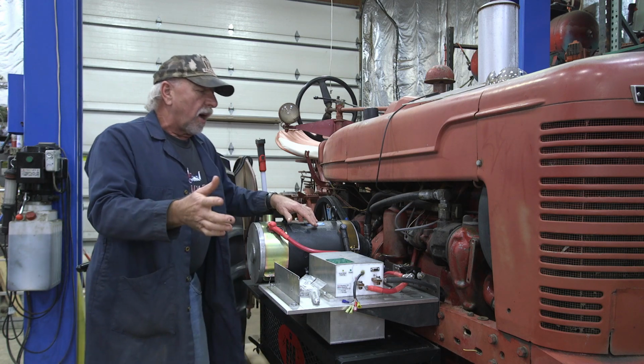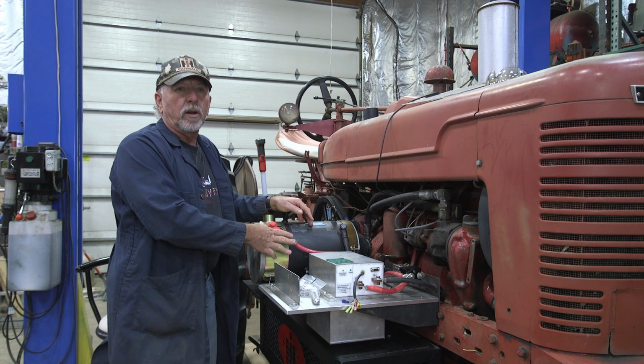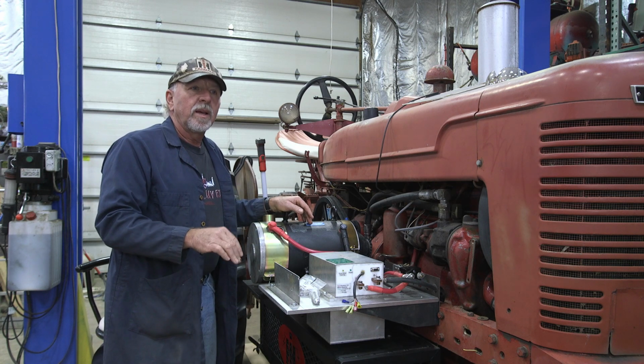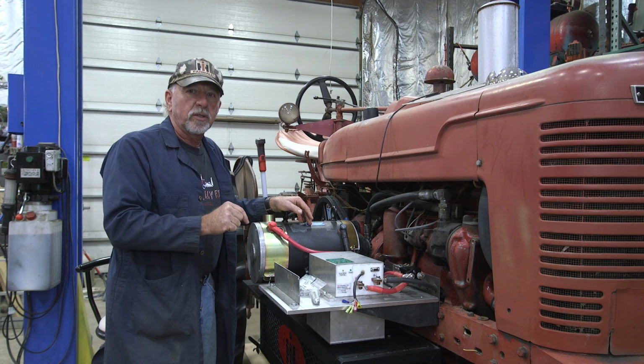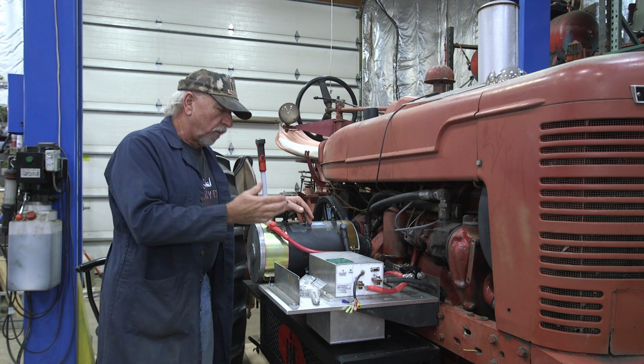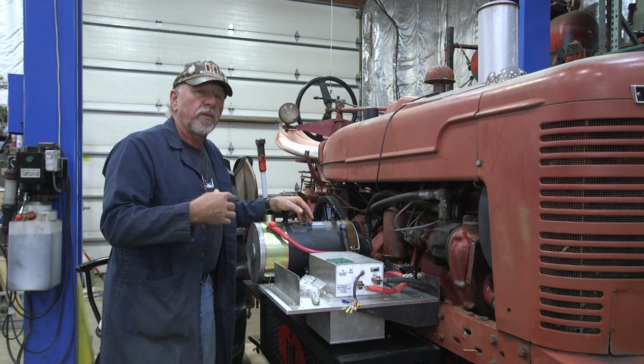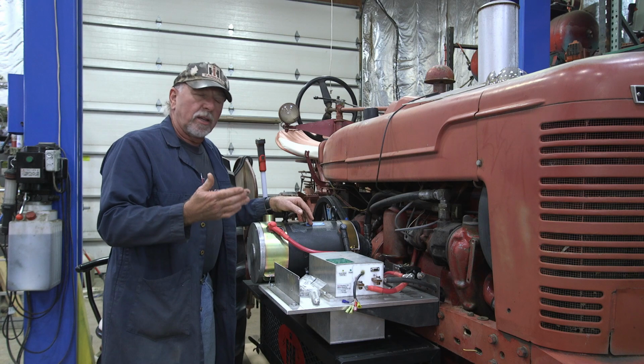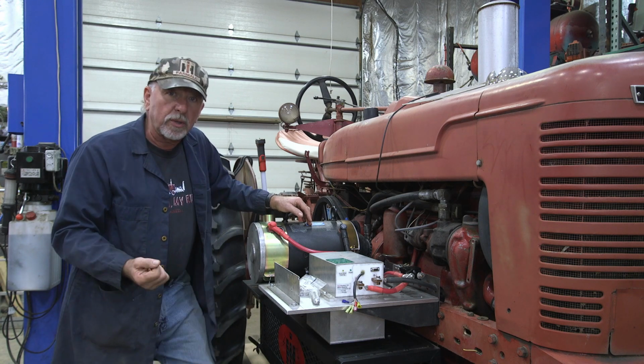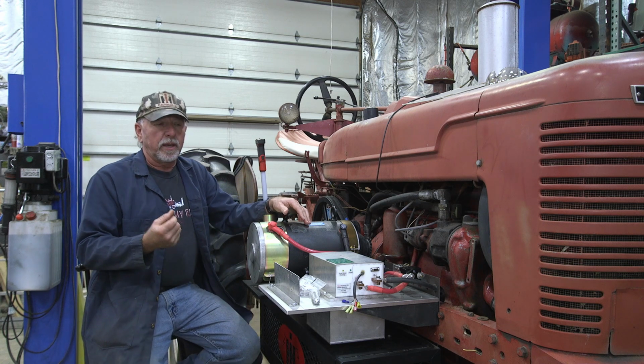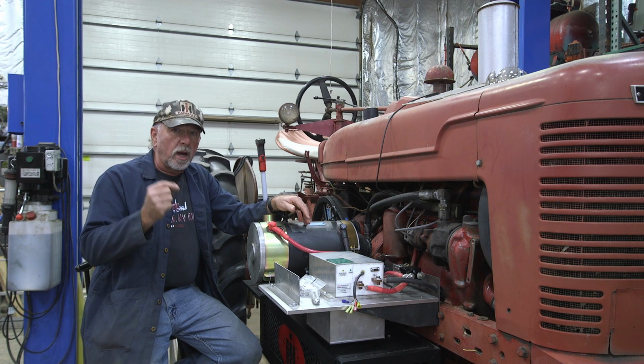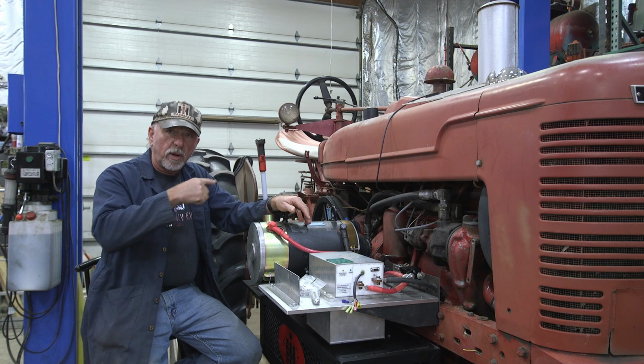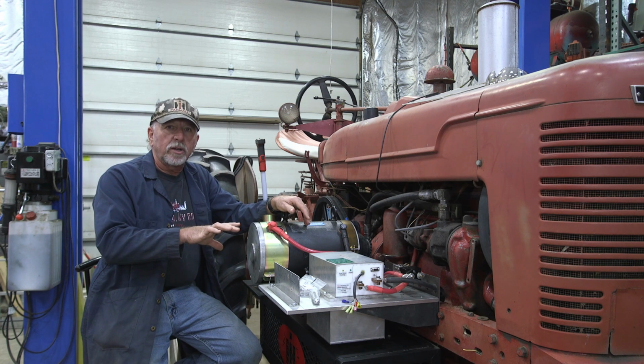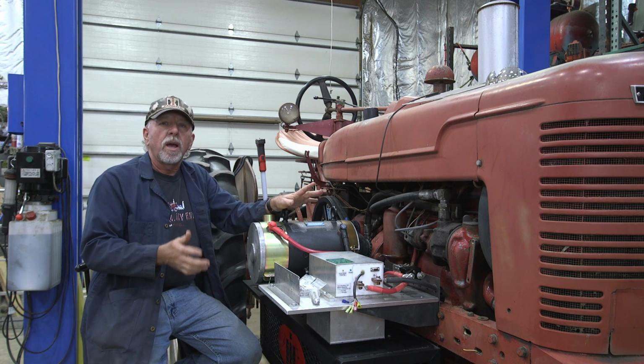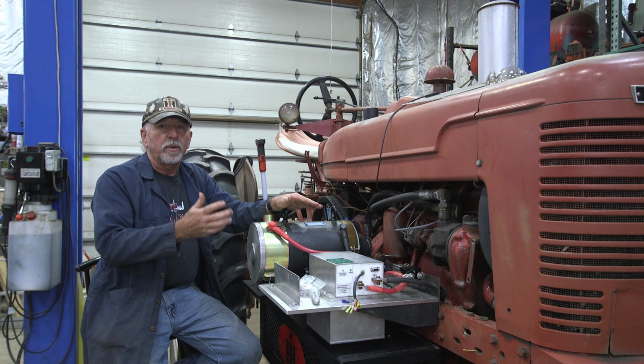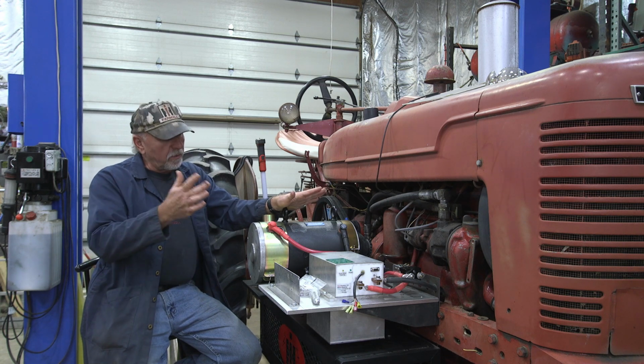So with that said, I started running in. Remember, the cables we put on here are 2/0 marine gauge cables. I went with a high quality copper, very weather resistant as far as climate and chemicals, extremely high grade. The goal here is to have the least amount of voltage drop as possible. With the calculations, we should be running at darn close to zero voltage drop throughout the whole circuit under a moderate load. Under a severe load, of course, it's a linear relationship. I feel pretty confident going with that style and quality of cable.